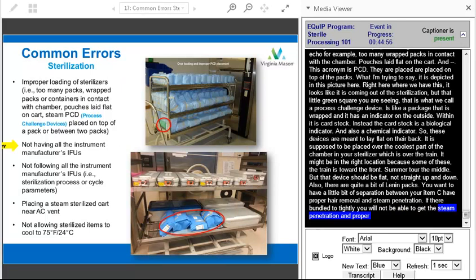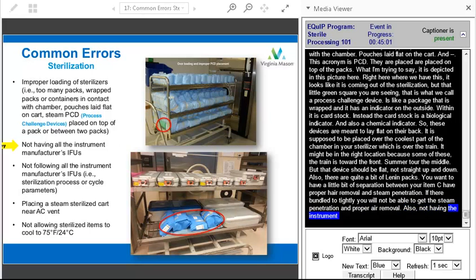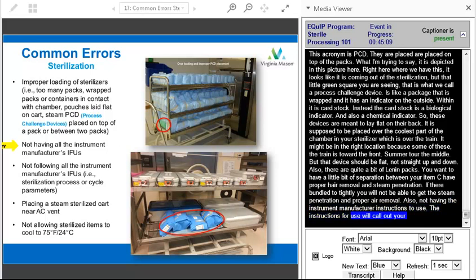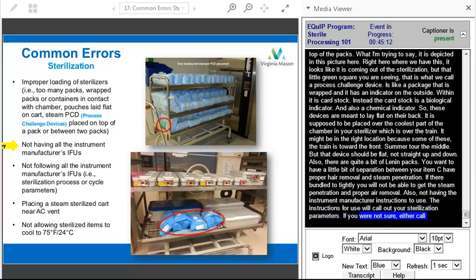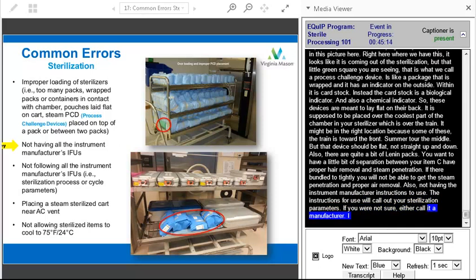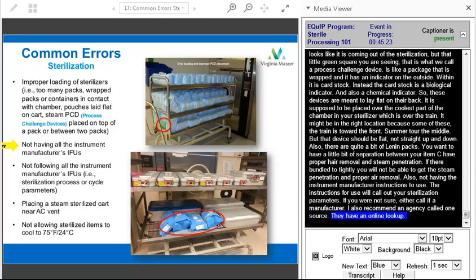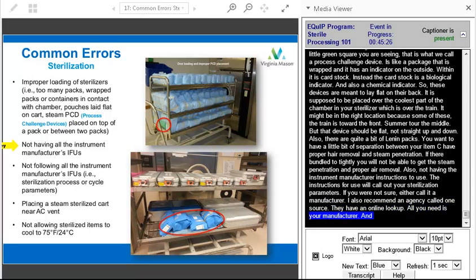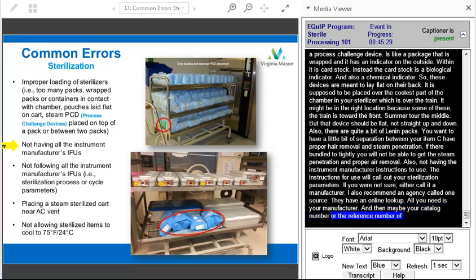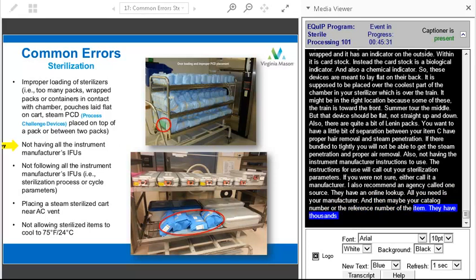Also, not having the instrument manufacturer's instructions for use is another one, because the instructions for use are going to call out your sterilization parameters. So if you're not sure, either call the manufacturer. I also recommend an agency called OneSource. They have an online lookup, and all you have to have is your manufacturer and then maybe your catalog number or the reference number of the item, and they have, I think, thousands of manufacturers' instructions for use in their database that you can electronically pull up online at your fingertips. So those are actually really nice.